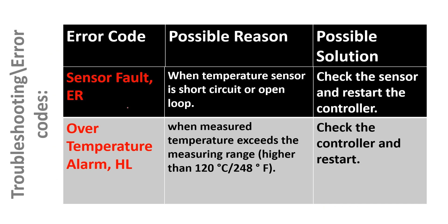These are the error codes this controller will display. When the ER error code is displayed, it means a sensor fault — the temperature sensor is short-circuited or open. The solution is to check the sensor and restart the controller. When HL is displayed, it means an over-temperature alarm — the measured temperature has exceeded the measuring range. The user needs to take corrective action and restart the controller.